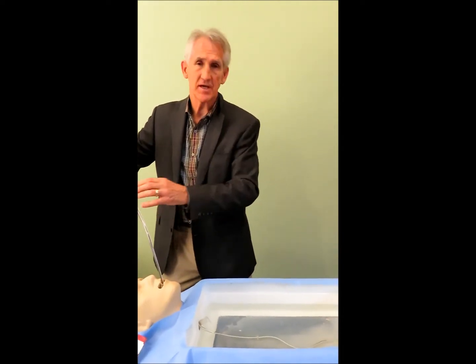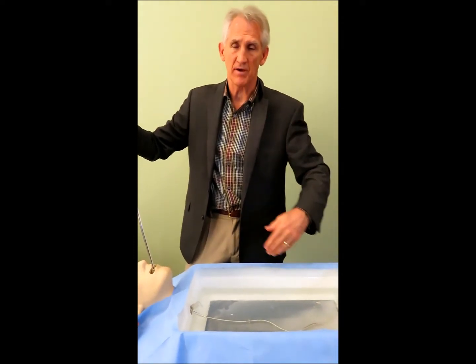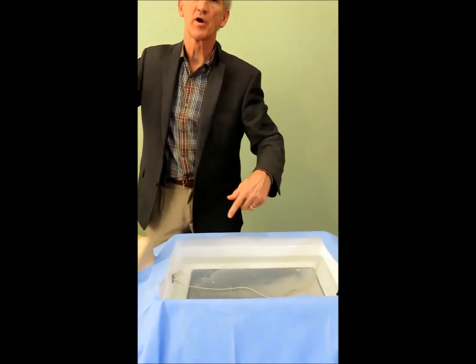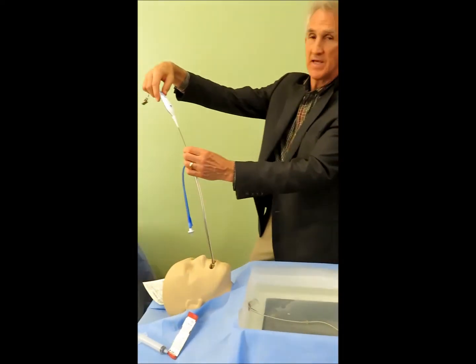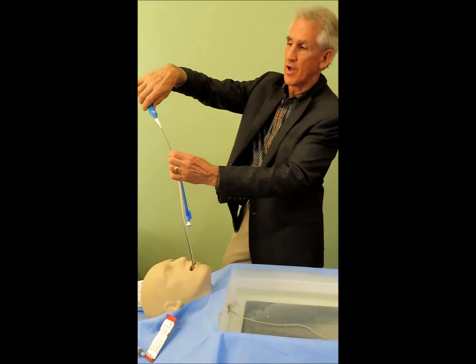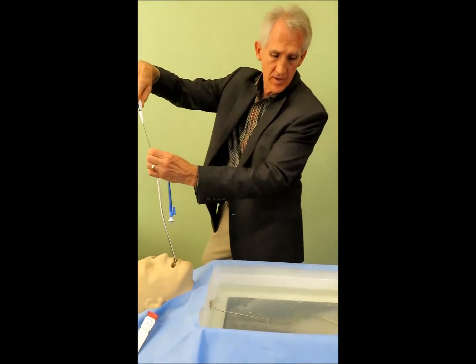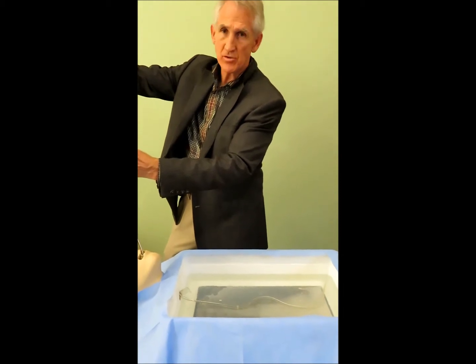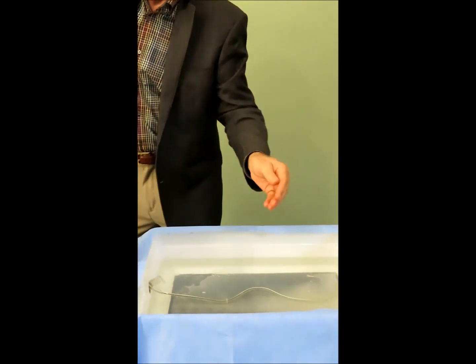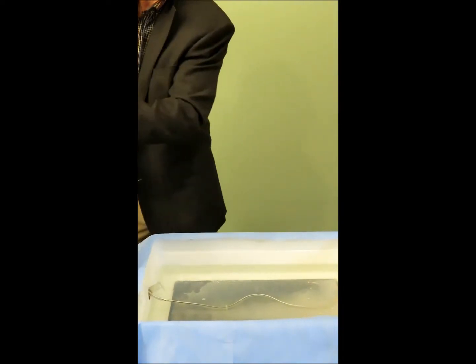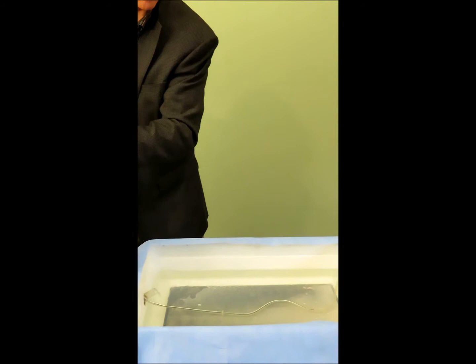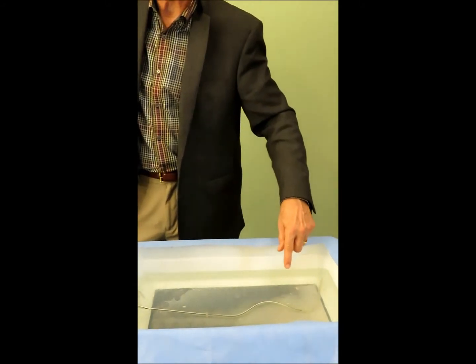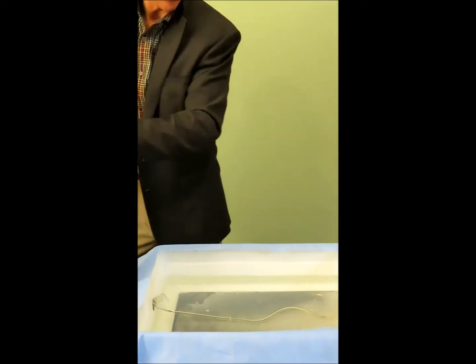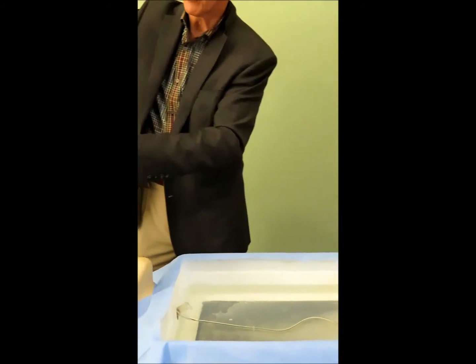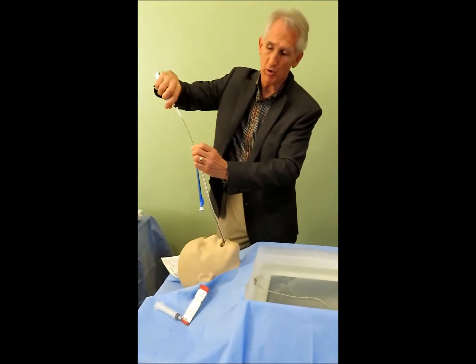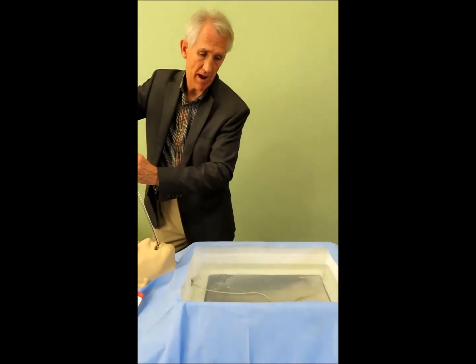Now, if we're putting it down, and say it's a repeat procedure and the doctor wants the curve to the left, if we put it down and the curve is to the right, we're going to need to rotate it over. So, take the handle and just rotate the handle about 3 full times, and then gradually pull back the Esosure, and as you pull it back, the tension in that will cause the stylet to flip over to the other side, and then slide it down into position behind the left atrium with the curve on the left. Okay? Now, if we need to go back to the other side, just rotate it again. Rotate it 3 times, gradually pull it back. When it flops over, slide it back down.